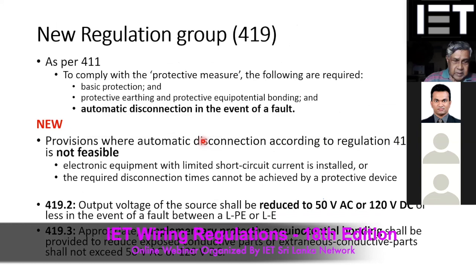And also there are certain major revisions and new regulations added to the standard. When you look at this, 419 is a complete new section added to the standard. As per the earlier version, when we want to have the protective measure, the protective measure is defined as you have to provide the basic protection. So now we are not using the term protection against direct contact and indirect contact. The basic protection is now a compulsory protection requirement. And then you have to have the equipotential bonding and the automatic disconnection.